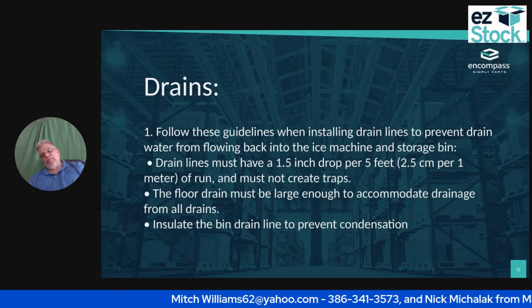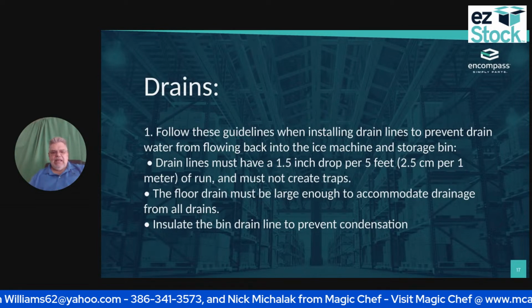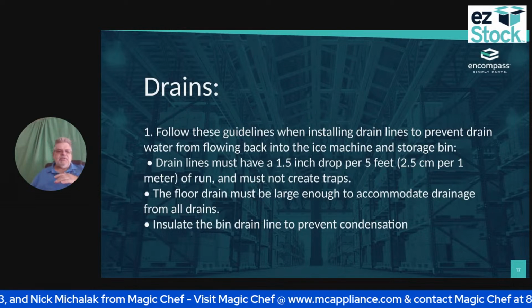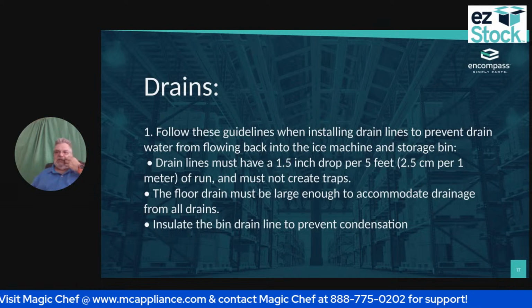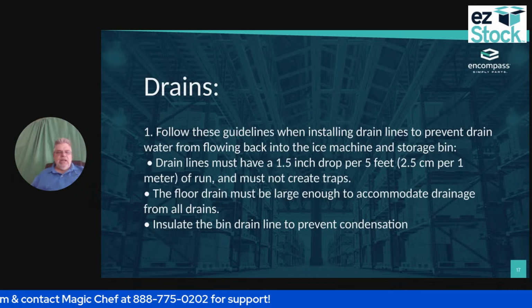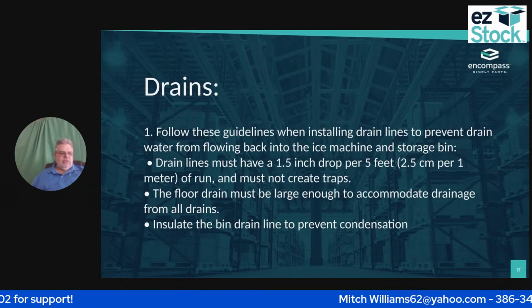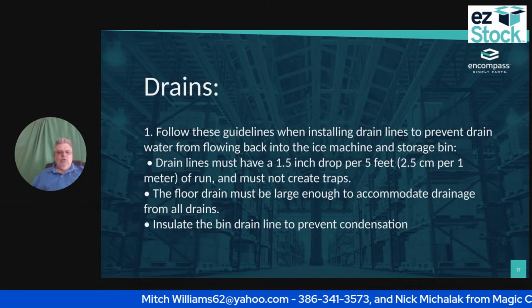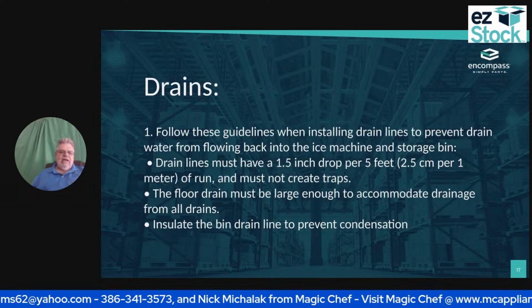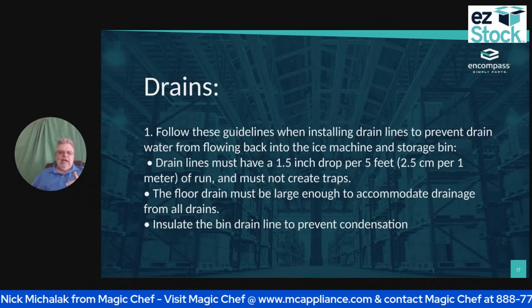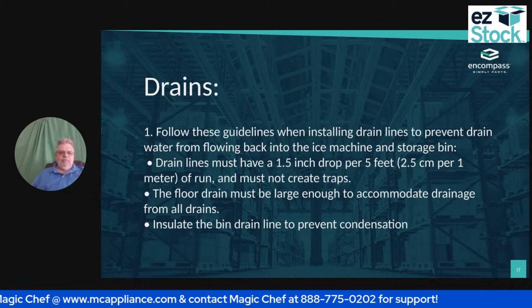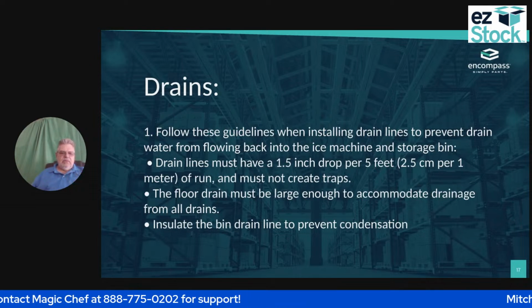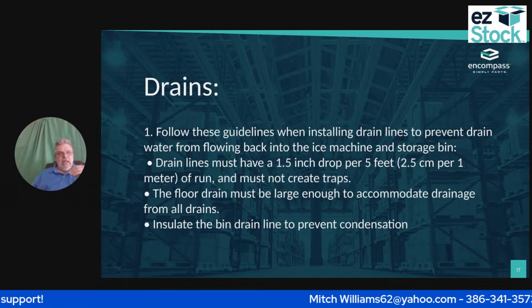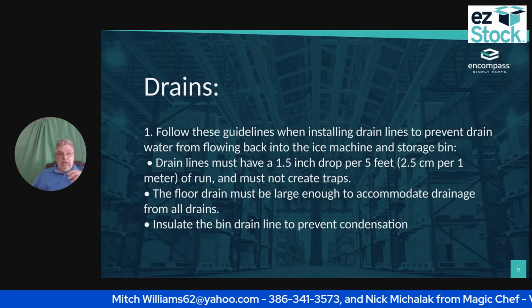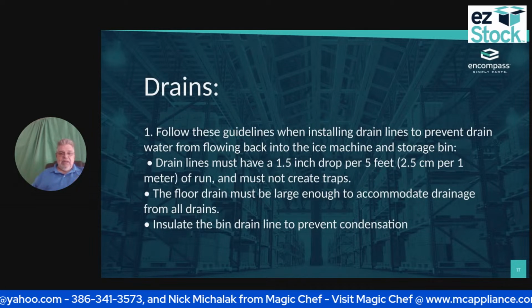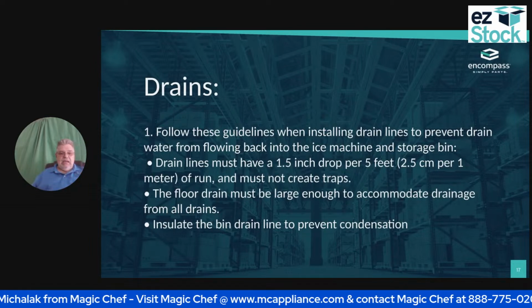I always carried in my truck about 6 feet of tubing insulation for my tubing. Okay. Drains, super important. So I have to follow these guidelines whenever I'm installing a drain. This is the biggest problem that anybody has with a brand new installation. The unit has been in for 3 months, and all of a sudden they seem to have this huge problem of water backing up into the drain. So what happens? A drain line must have a 1.5-inch drop per 5 feet, which is 2.5 centimeters per meter. Okay. And it can't create a trap. If somebody has gone in and put in rubber tubing, which happens all the time, it creates a trap. It's not flat and then it runs, okay?